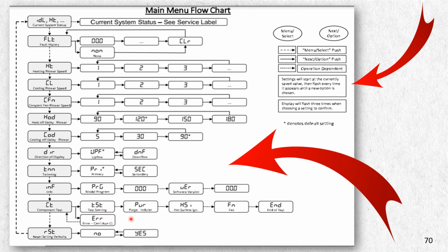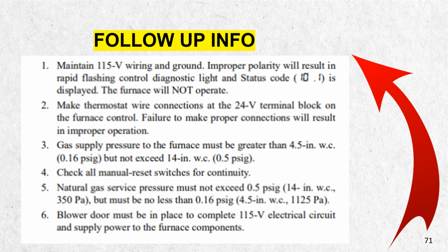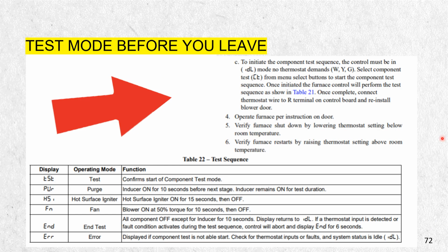You can do your testing if you're going to do a component test. This is what ICP recommends: once you get it to be a final install, you need to actually run a component test on it and make sure everything goes through its cycles. And then to follow up, maintain you have 115 volts and not 208, 230. And if you don't have the right polarity, you will see a 10.1. That means tighten your wires up and make sure you got a good ground. Make sure you have 24 volts. Minimum gas pressure is 4.5 coming in, maximum 14.